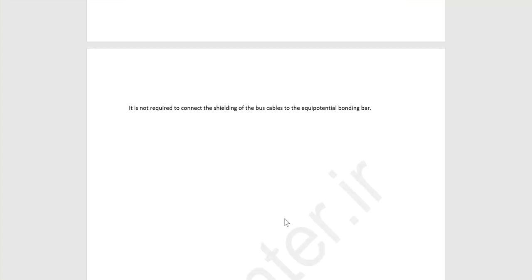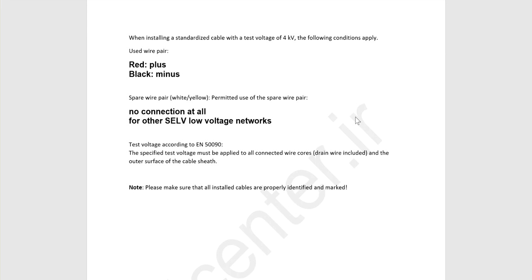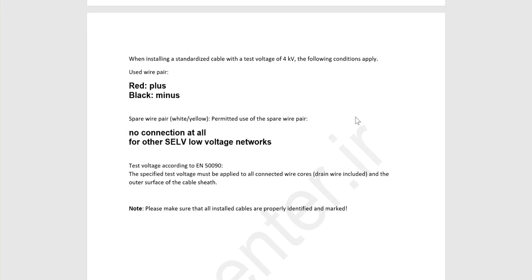Anyway, that's it. An important thing in the book says it is not required to connect the shielding of the bus cable to the equipotential bonding bar. As I said, we do not connect the shield of the KNX cable to the earth, so we do not connect it to the bonding bar. In other protocols, for example devices in BACnet, we always connect it to the bonding bar.